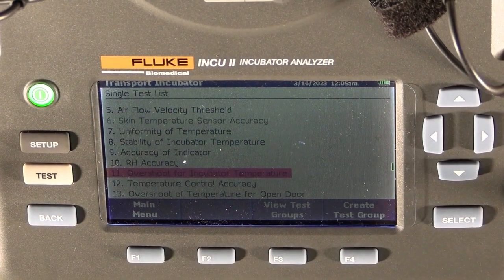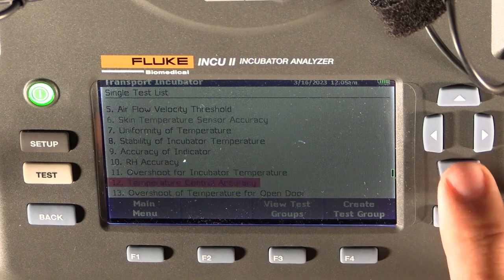The difference between the two, or the way of testing both of them: for the first overshoot, you close the hood, leave all the tools inside, switch on the machine and wait for it to reach its temperature, and then we measure the overshoot. The overshoot with open door is, once we've measured the first overshoot, we then open the incubator door for 10 minutes to let the air out while the incubator is still on, and then we close the door again and measure the overshoot that might occur when the temperature tries to return back to normal.